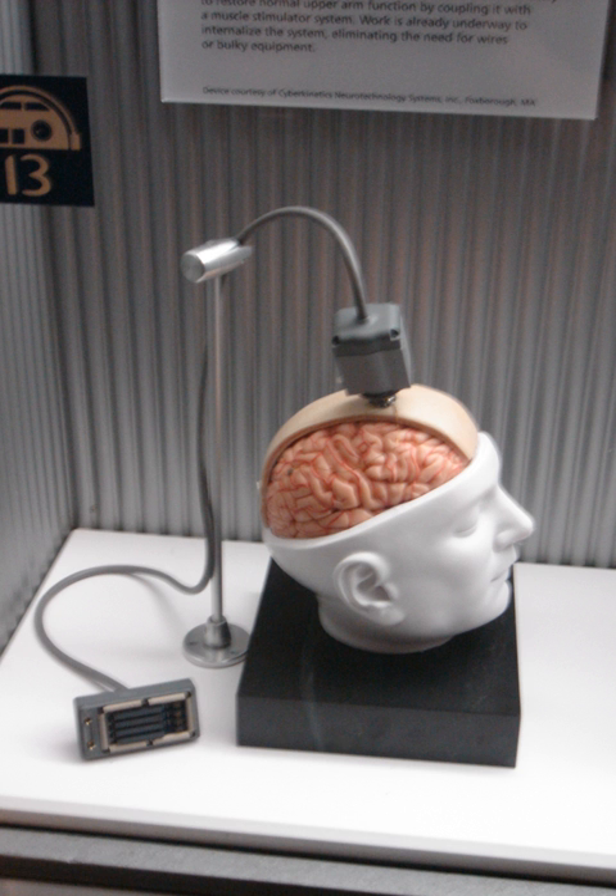A visual prosthesis can create a sense of image by electrically stimulating neurons in the visual system. A camera would wirelessly transmit to an implant; the implant would map the image across an array of electrodes. The array of electrodes has to effectively stimulate 600–1000 locations, stimulating these optic neurons in the retina, thus creating an image. The stimulation can also be done anywhere along the optic signals pathway. The optical nerve can be stimulated in order to create an image, or the visual cortex can be stimulated, although clinical tests have proven most successful for retinal implants.